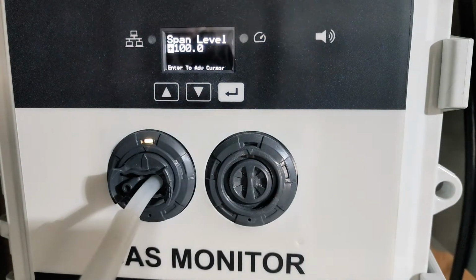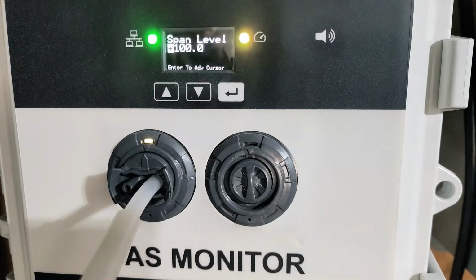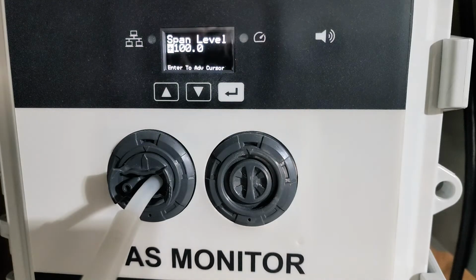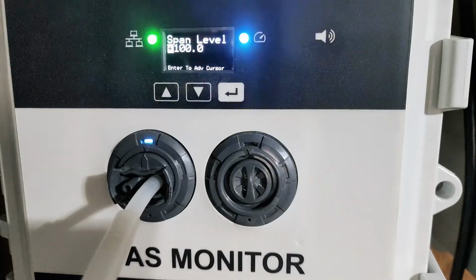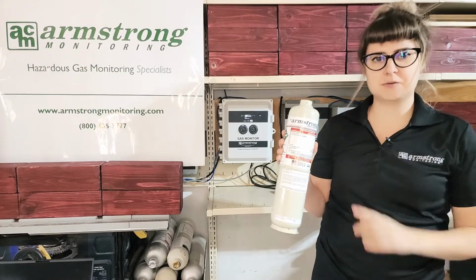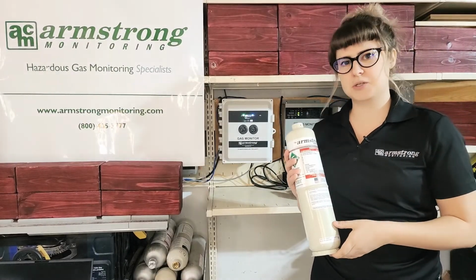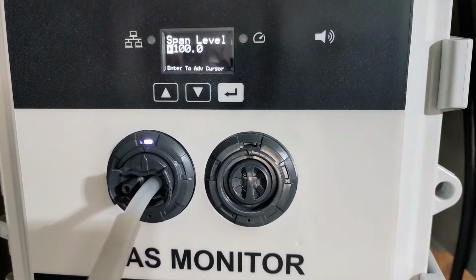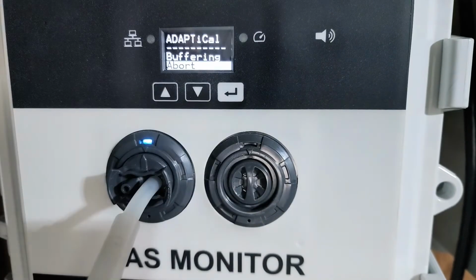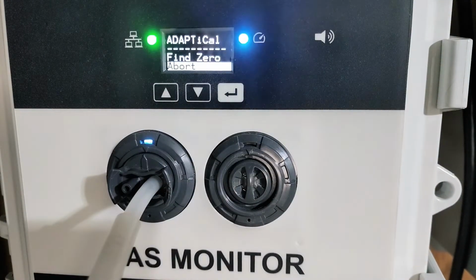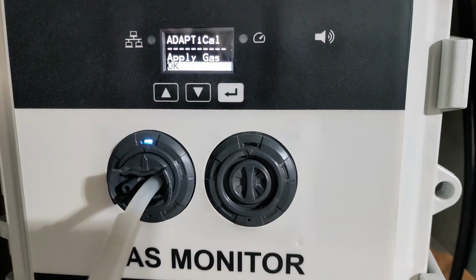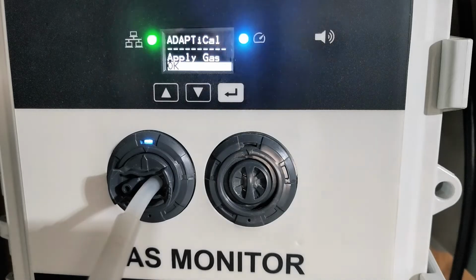It'll then prompt you to enter your span level concentration, which is the concentration of your target calibration gas. In my case, I'm using 100 ppm CO to calibrate the sensor module. So here I'll enter 100 as my span level. It will then enter a buffering phase and then find zero using the pure nitrogen applied. After it has completed the zero step, it'll then prompt you to apply your span gas. At this point, you can remove the pure nitrogen.